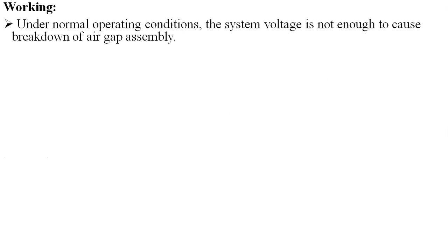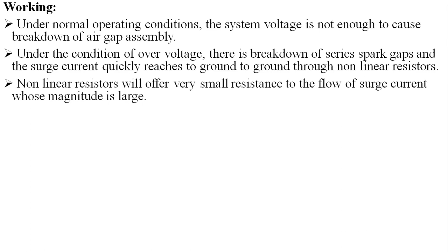Its working: under normal operating conditions, the system voltage is not enough to cause a breakdown of the air gap assembly. Under the condition of over voltage, there is a breakdown of series spark gaps and the surge current quickly reaches ground through the non-linear resistors. The non-linear resistors will offer very small resistance to the flow of that surge current whose magnitude is large. Thus, when the surge is over, the resistor blocks offer a high resistance to the flow of current and the current is interrupted.